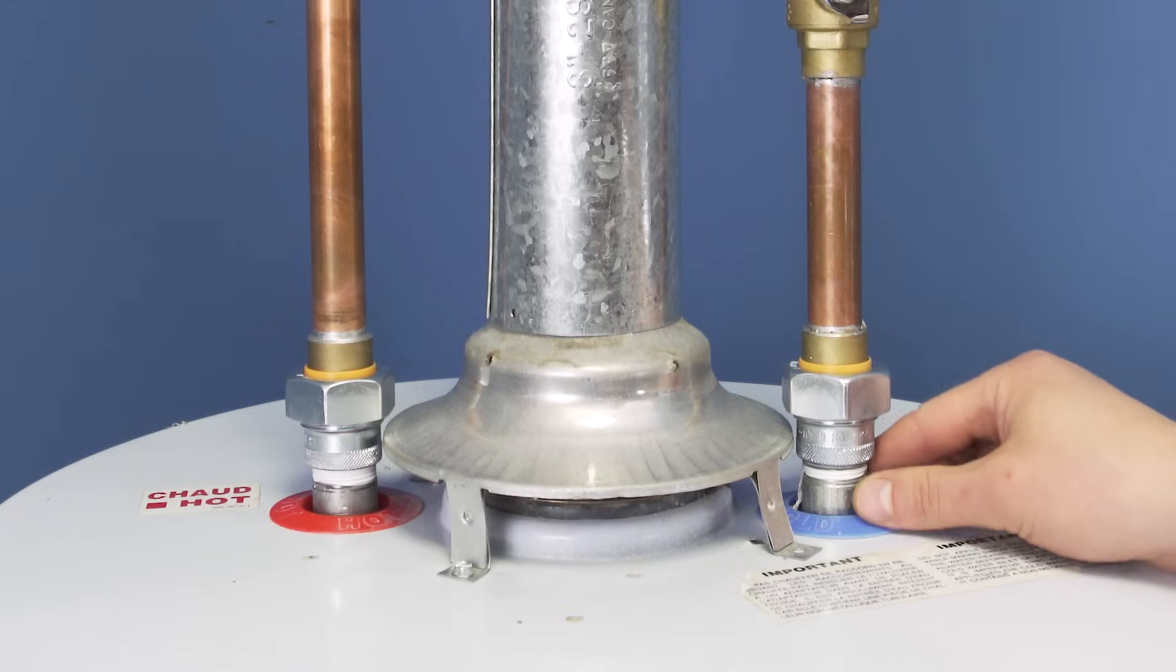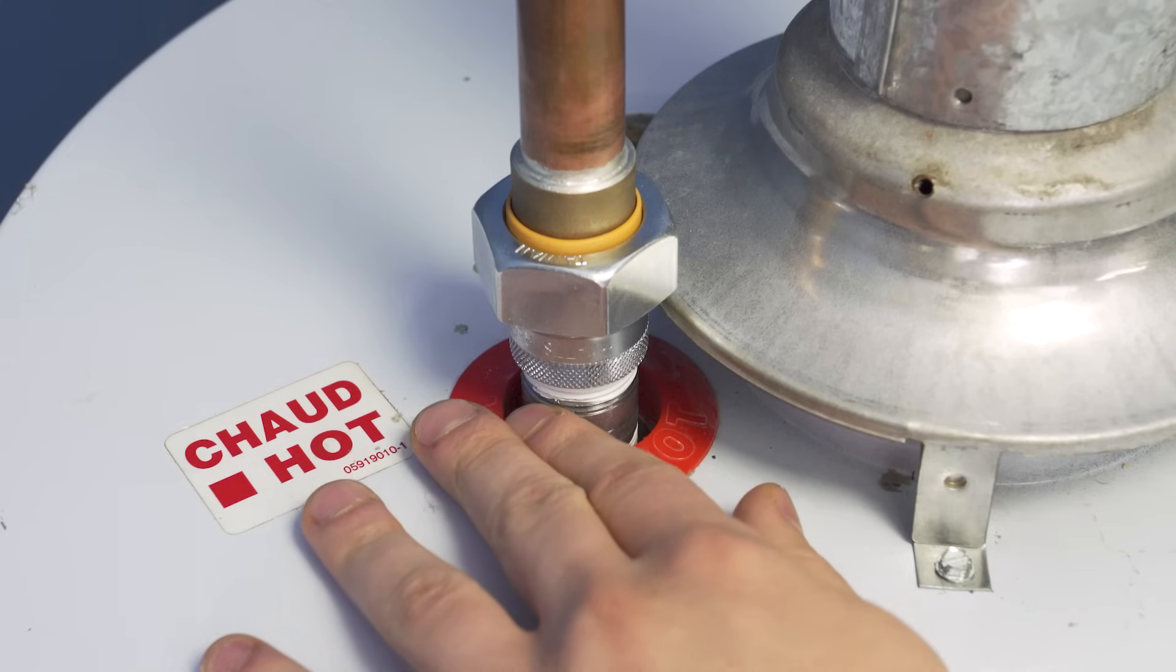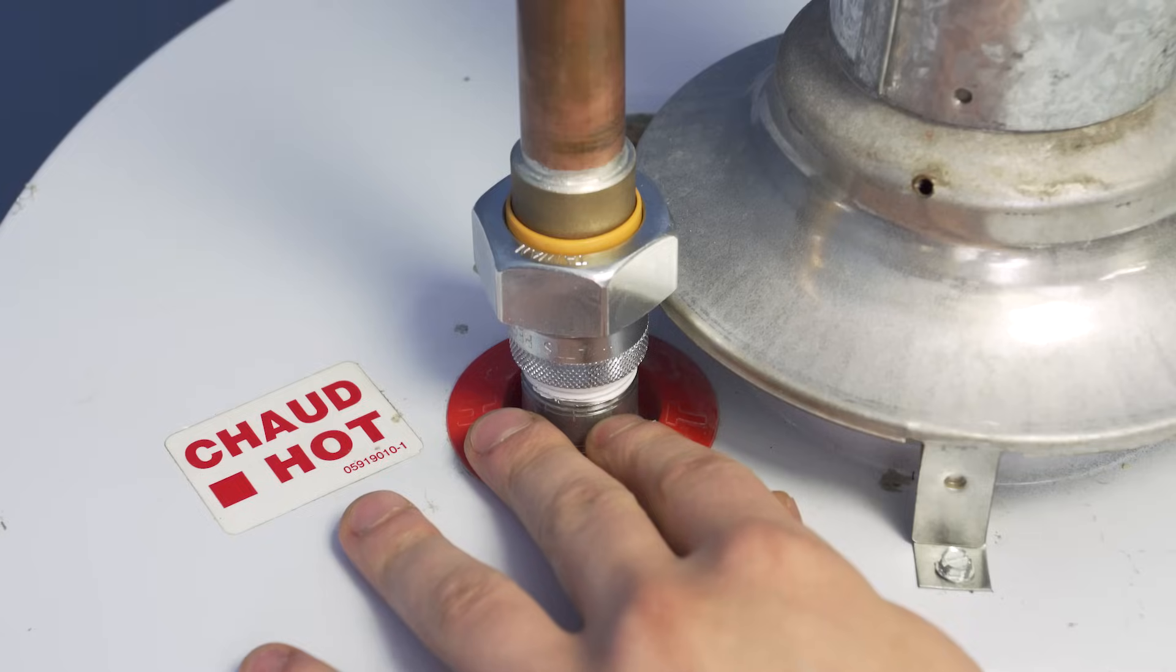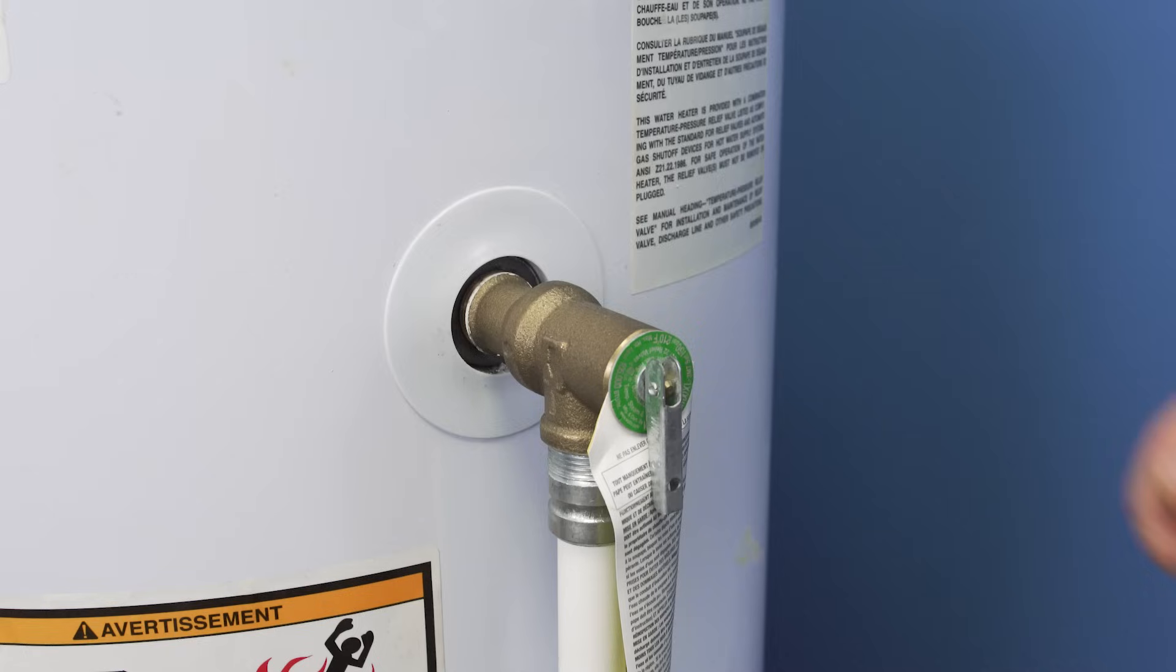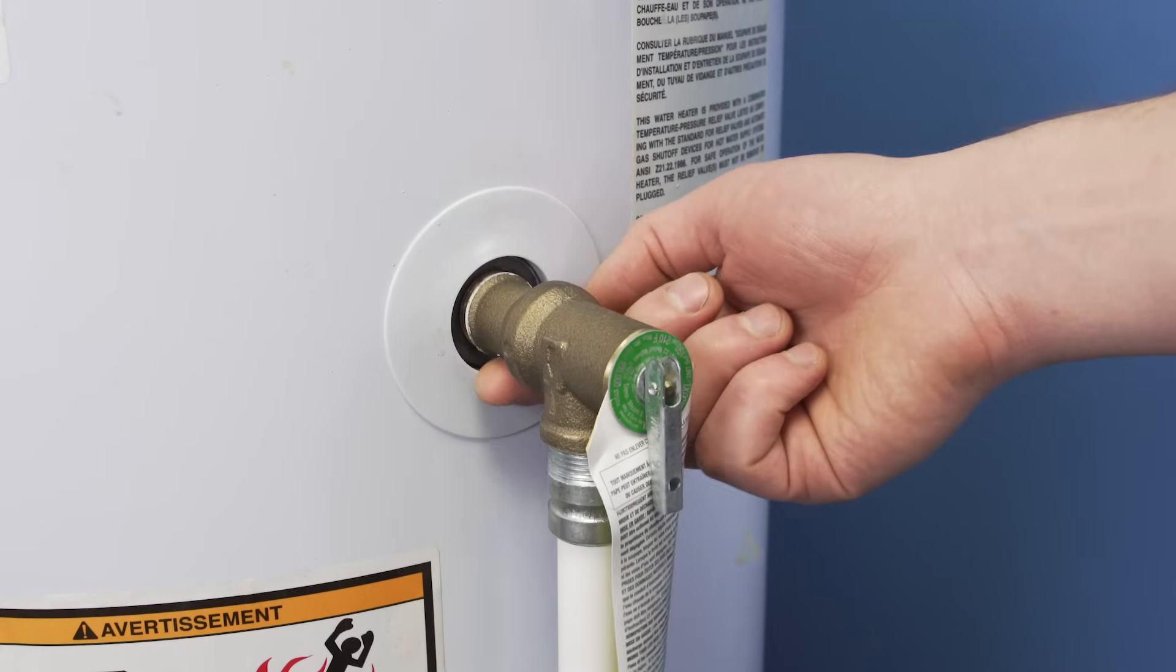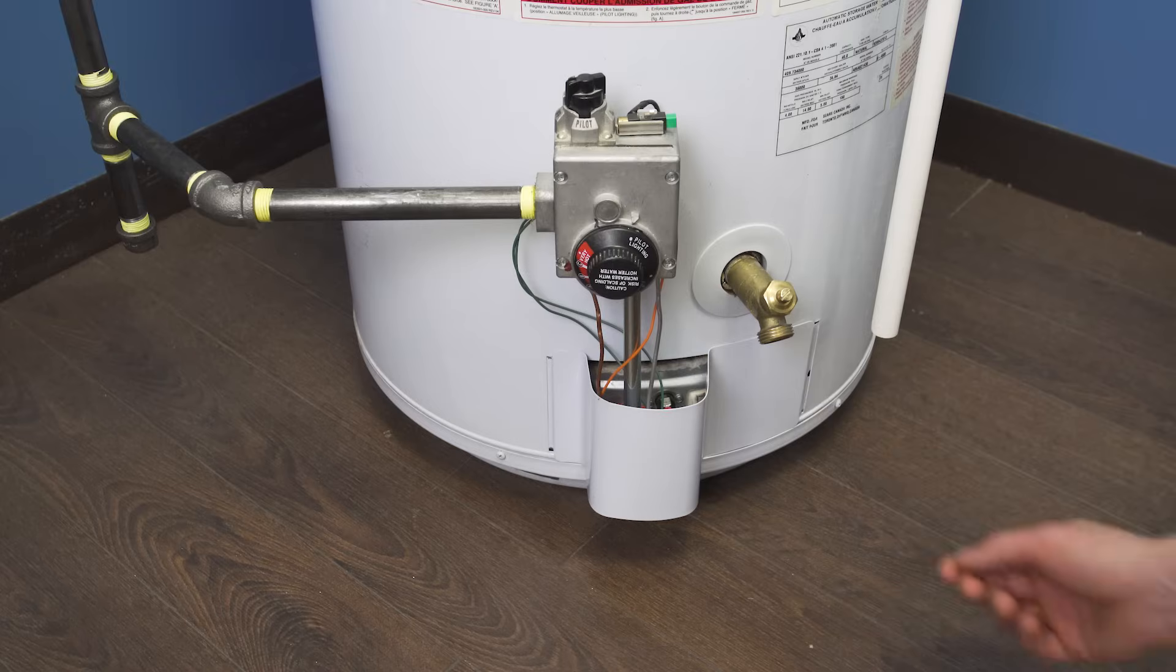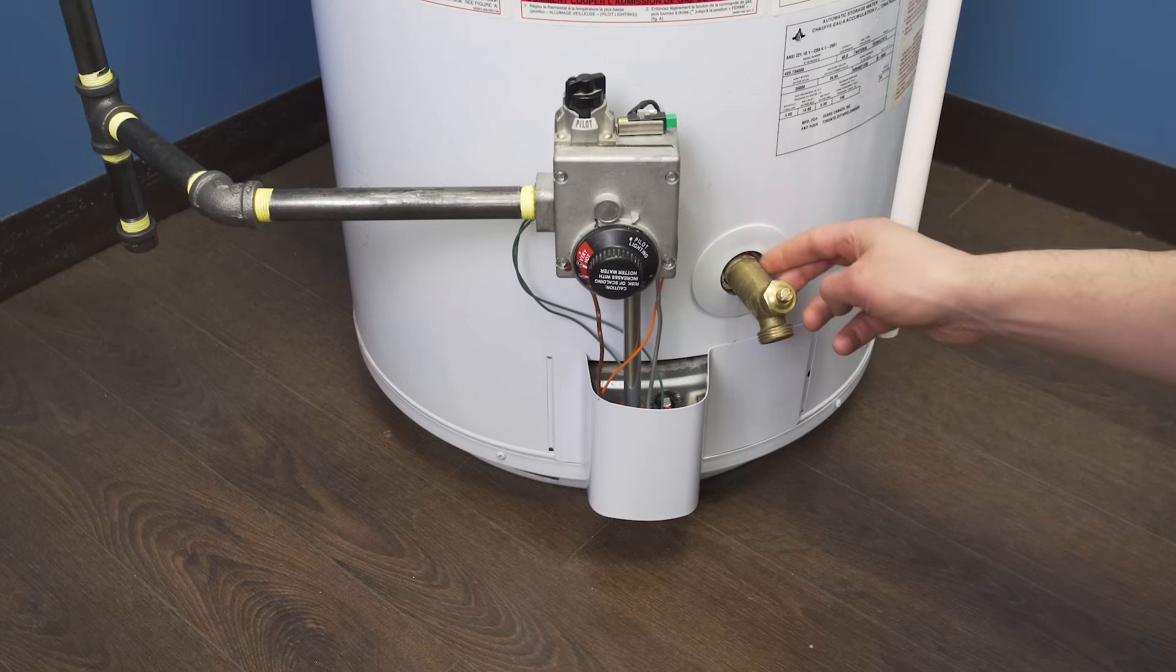To start it's best to do a walk around to check for any leaks. Check the inlet and outlet pipes leading into the tank. Next check the pressure and temperature relief valve, looking for any water weeping around the threads, or around the valve body. Now look at the drain valve. If you see any water leaking, it's best to replace that part.